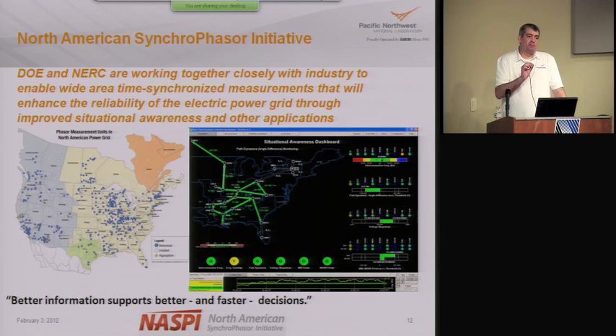One tidbit to remember about the blackout: once at 4:10 in the afternoon the system was so far gone that things were happening as an uncontrolled cascading failure, it was too late for a human to take action, automatic controls were doing their thing. But from 3:05 to 4:10 in the afternoon, over about an hour, the system was outside the stability constraints from all the contingency analysis I talked about, yet nobody took action. The reason they didn't act is that they were having problems with their computer software, which prevented them from having what we call situational awareness of what was going on.